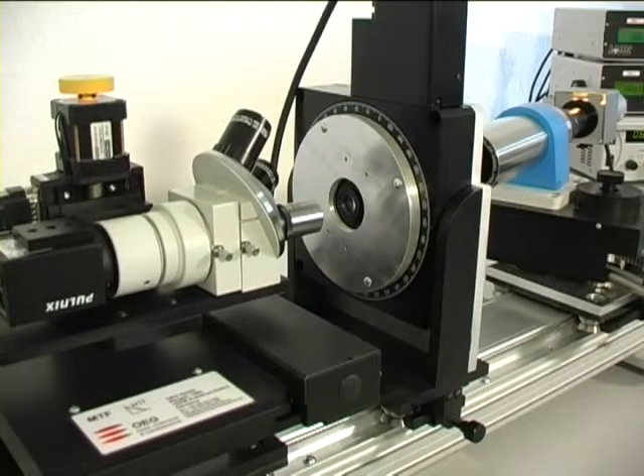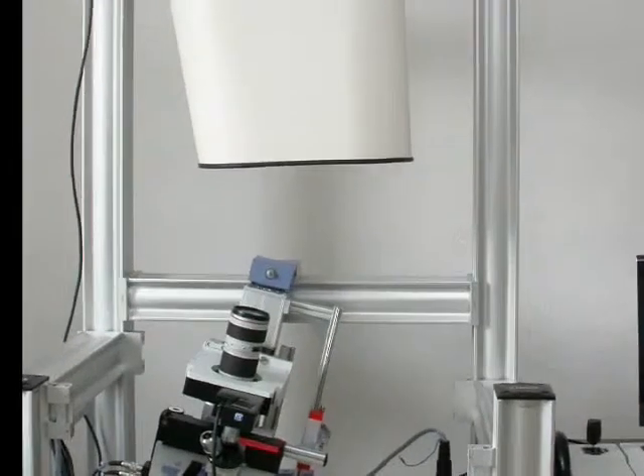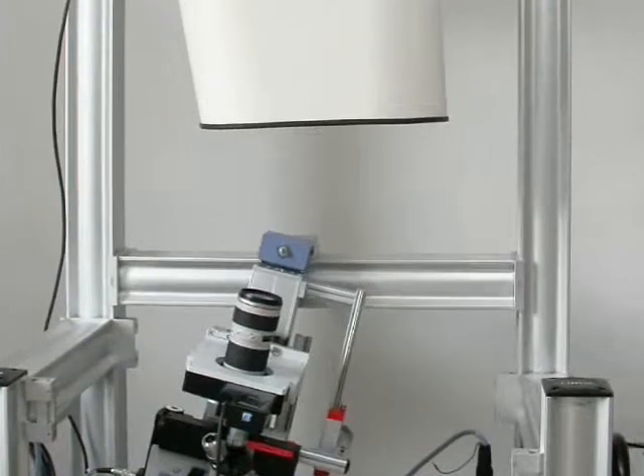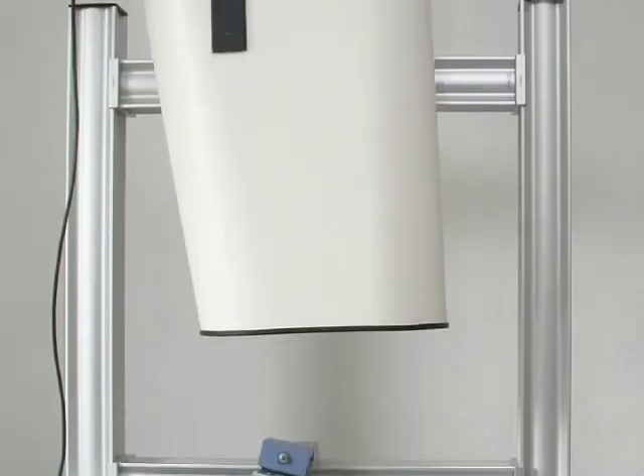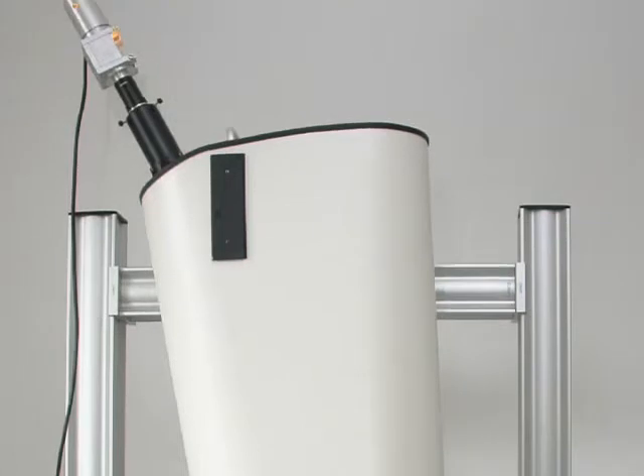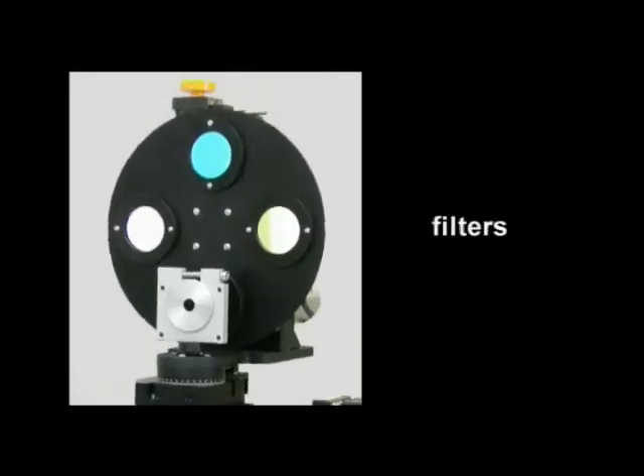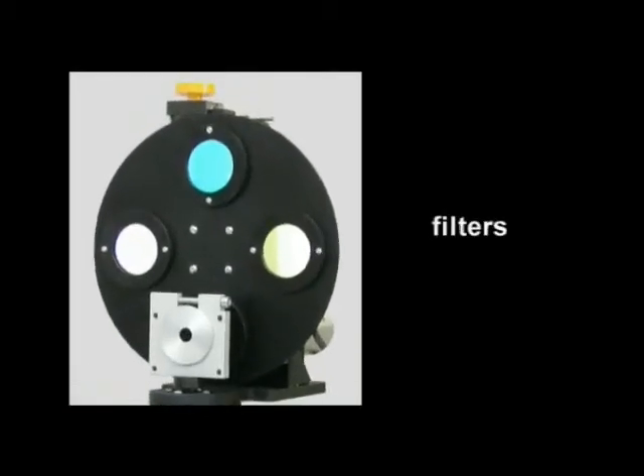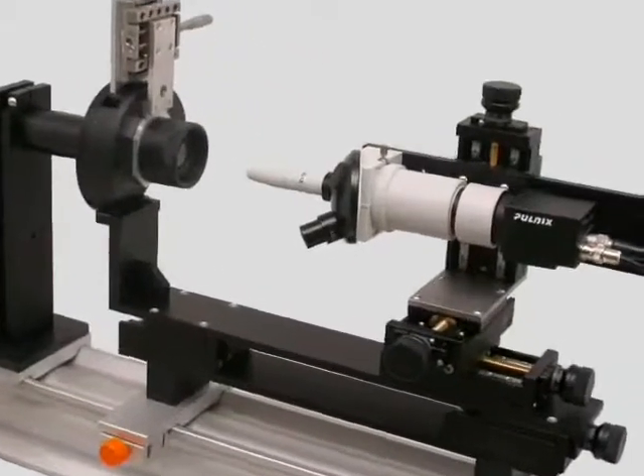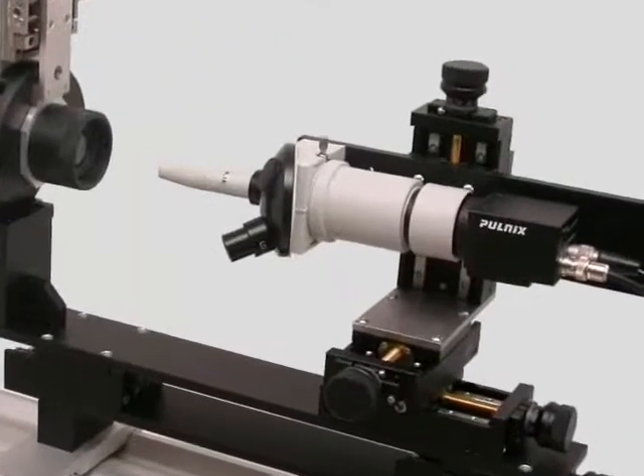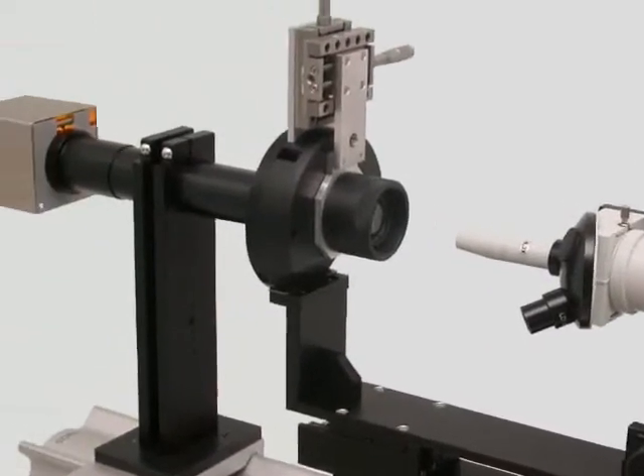MTF variant offers universal interfaces for data export into other applications. It can be adapted to almost all special measuring tasks, concerning for example the length of the stages, the free opening of the precision turntable, the focal length and free aperture of the collimator, the measuring wavelengths, and the working distance — including the measurement of image intensifier tubes as one example for special solutions.